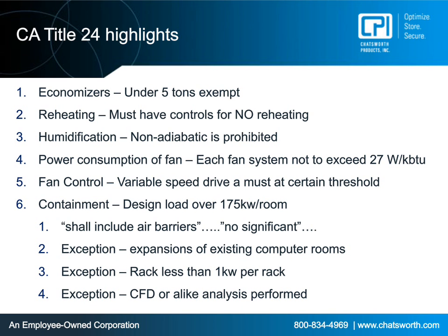Humidification cannot be non-adiabatic, meaning you cannot just heat up the water to make mist to get your humidification. California has a maximum limit on your fan speeds. Your fan control should be variable speed. Most of the customers are already onto this variable speed fan control. So instead of just having a fan that's on or off, if you can ratchet that fan down just slightly, you can still get almost identical airflow with a lot less energy, and save quite a bit of money by just varying the speed of your fans.